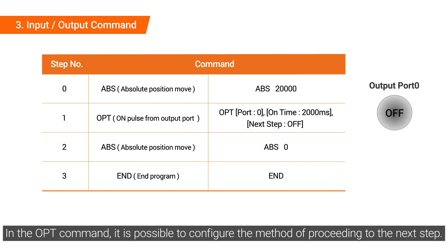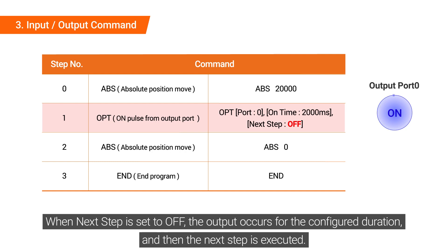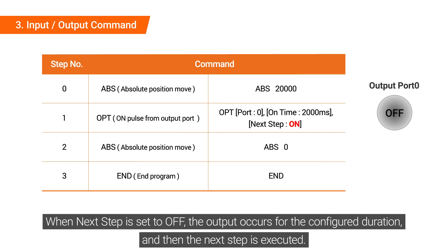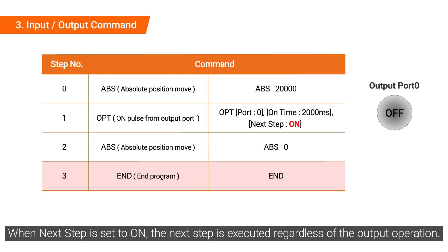In the OPT command, it is possible to configure the method of proceeding to the next step. When next step is set to off, the output occurs for the configured duration and then the next step is executed. When next step is set to on, the next step is executed regardless of the output operation.